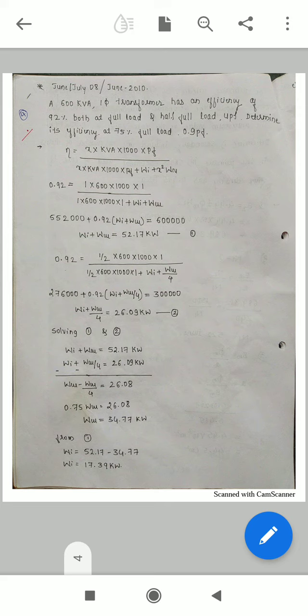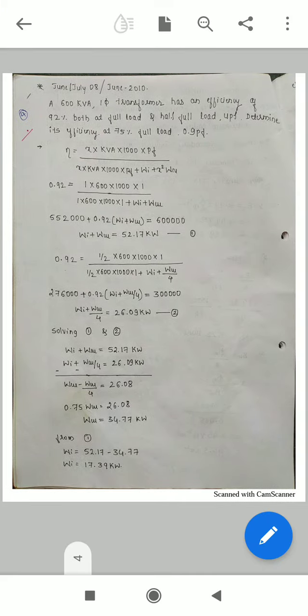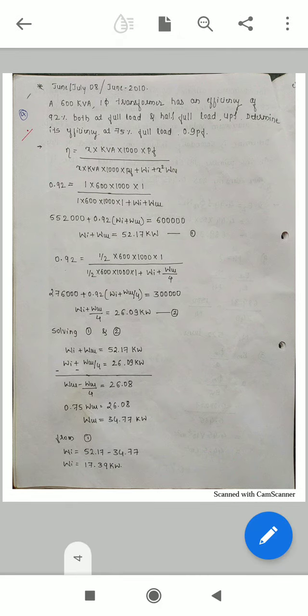In this problem, we are given a 600 kVA single-phase transformer that has an efficiency of 92% at both full load and half full load. This problem consists of two parts. The 92% efficiency is applicable for both full load and half full load. We need to determine its efficiency at 75% full load with 0.9 power factor.